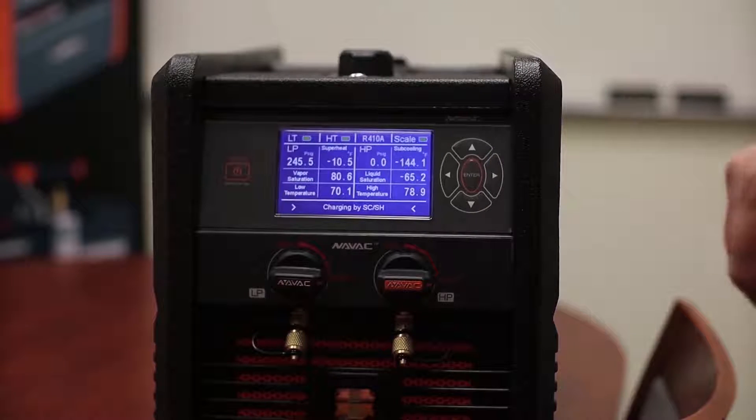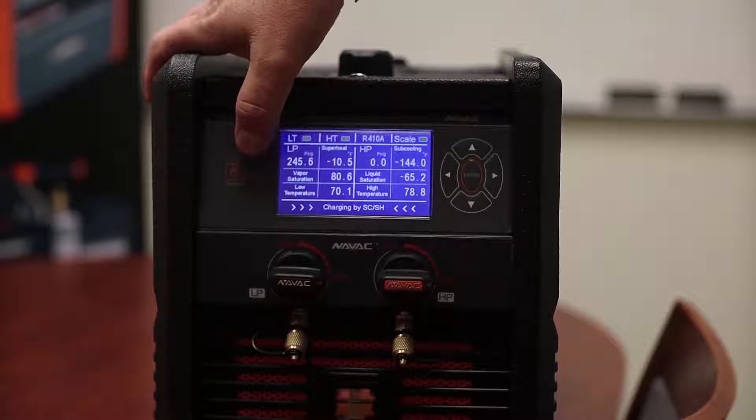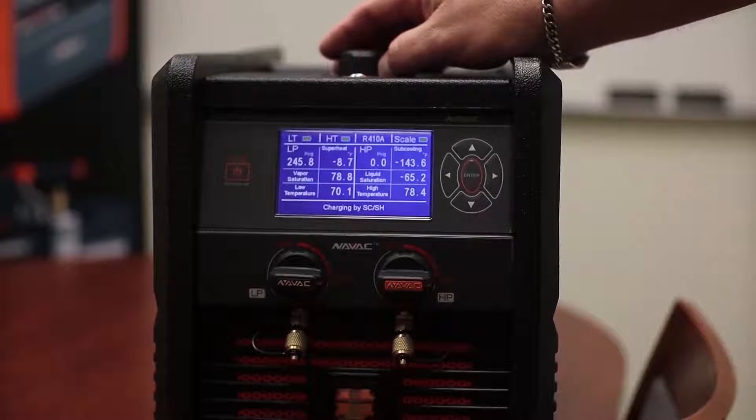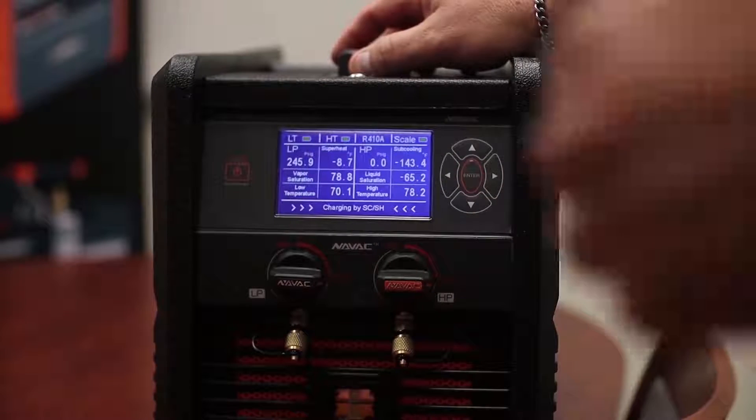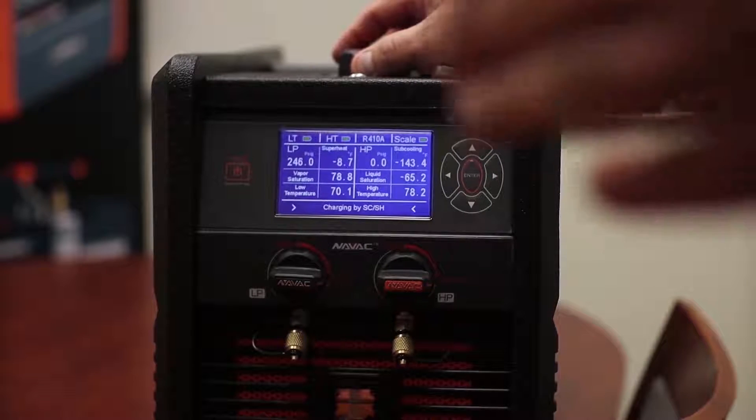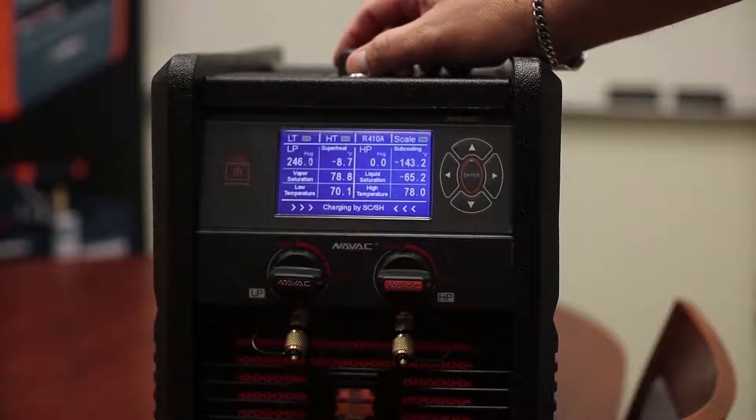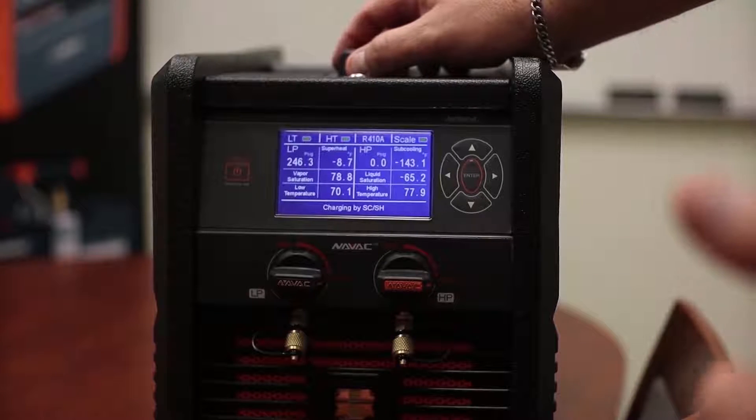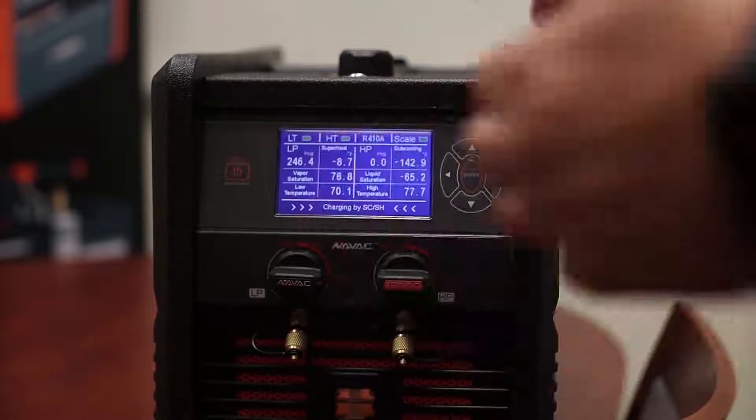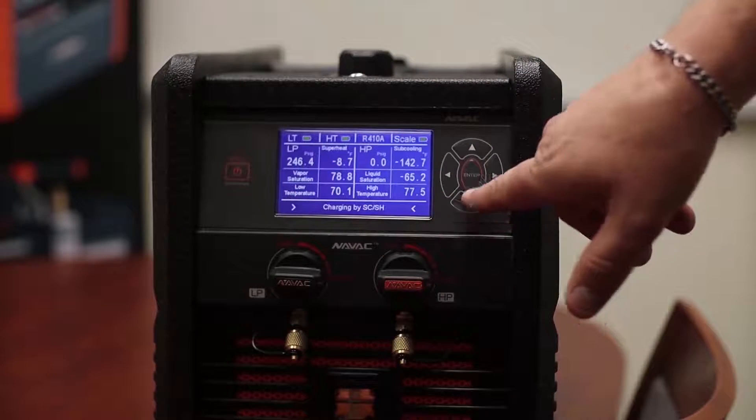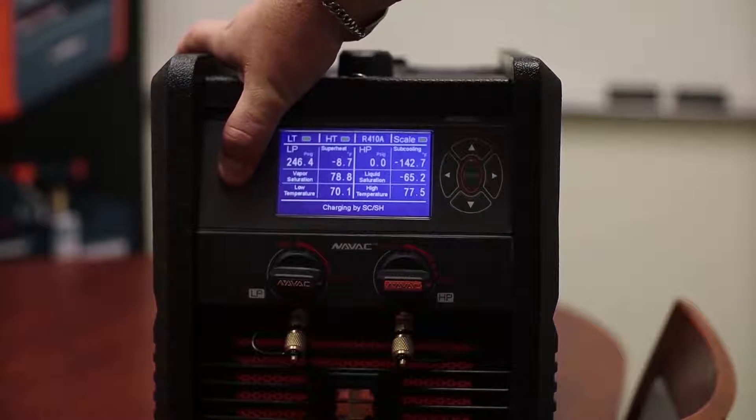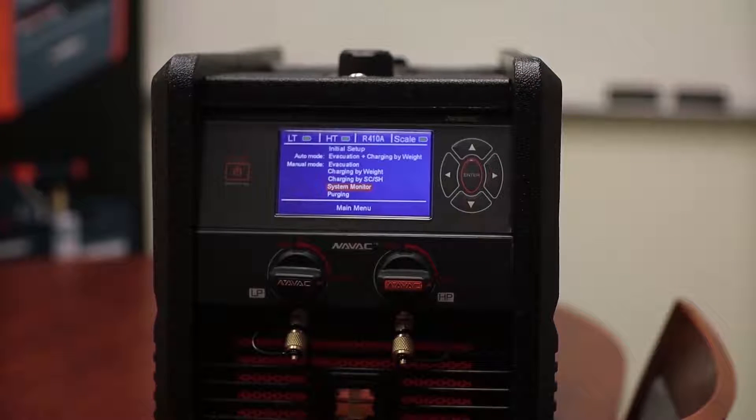So once it's completely charged, you can also, and I recommend this if you're on a job, you've got it charged, but you're still going to be on the job for a little while because we know that certain things, as the temperature comes down in the house, the humidity level changes, the 410A, the time it takes to balance, to adjust after you adjust the charge. Then we're going to go back to our main menu, and I'll show you another feature that we have here, and that is system monitor.